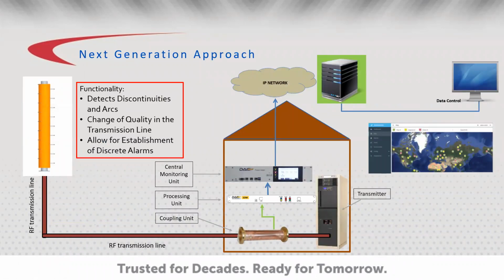So the next generation of real-time monitoring systems is to implement a system that can be retrofitted into existing sites. The system has the ability to detect and localize arcs and discontinuities due to changes in transmission line integrity. It will characterize the system over time, and it will also allow for discrete alarms to be established based on component characteristics. The system will operate full-time under full power conditions through the use of off-band injection.